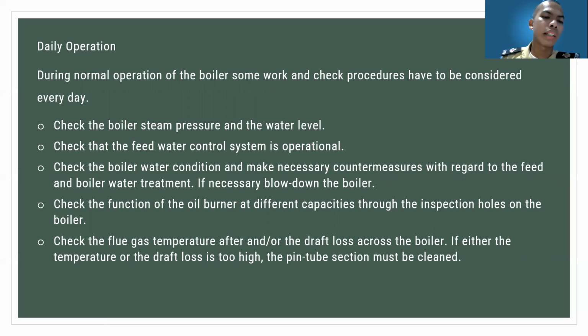And also we need to check the function of the boiler oil burners at different capacities through the inspection holes on the boiler. And also we need to check the flue gas temperature and the draft across the boiler, if either the temperature or the draft loss is too high. And also the pin tube section must be clean.